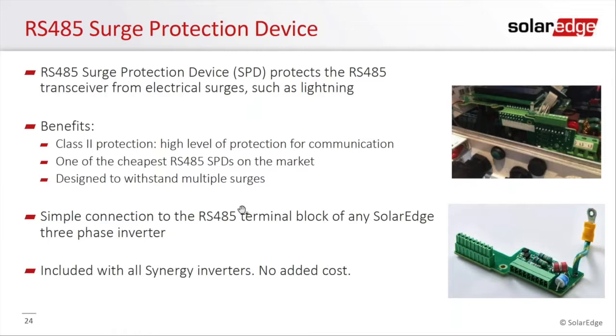The other place where we're helping on the risk mitigation and also reducing your costs for your project is the RS-485 Surge Protection Device, or SPD. As I mentioned before, we're shipping that with all of our commercial inverters, not just the Synergy, but all commercial inverters. And it's a little plug-in card that plugs into the COM board, and then you would connect your RS-485 daisy chain amongst the inverters. So it provides that extra level of protection. It is a class 2 level protection, and it's a very simple device to install.